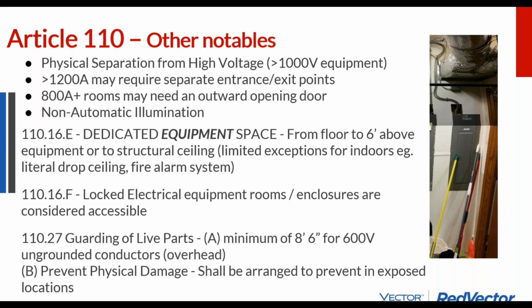And the other aspect of guarding of live parts is to prevent physical damage. And so that's another aspect of, well, when do you need metal conduit versus non-metal? That metal conduit is there to prevent physical damage. And so, if you're running power lines along a driveway versus up on a rooftop, there's a different requirement for physical protection. So you might not need to be in conduit up on the rooftop, but then you're right down on the driveway, now it's mandatory because of physical protection.